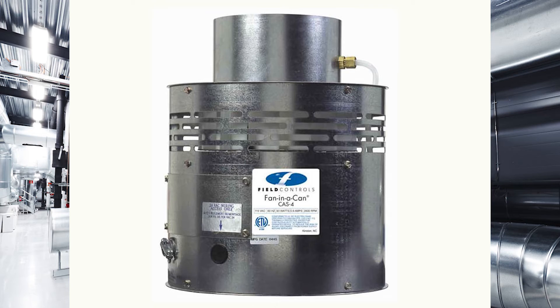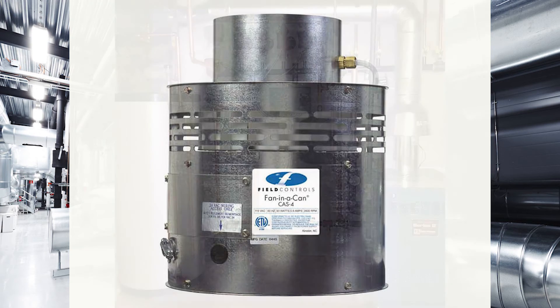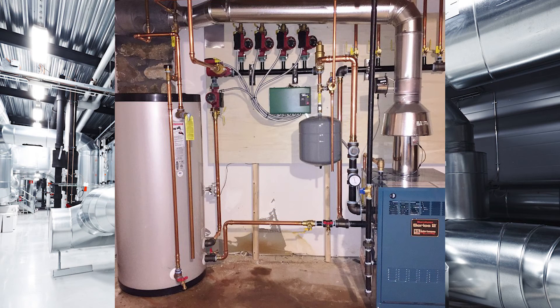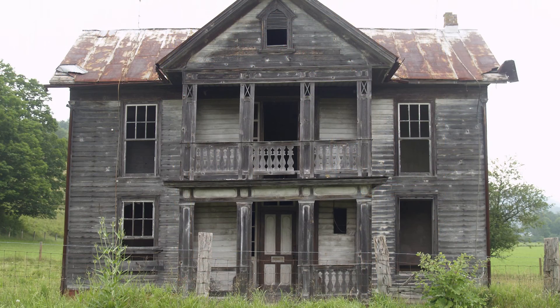For the record, anything over 50 feet will need to have mechanical air supplied, meaning you need some sort of fan to blow in the combustion air with an approved setup. This brings us to the end of this video. Stay tuned for video 3 of the air supply series, where we talk about loose constructed buildings and how to size air supply for that. Until then, have a great day.